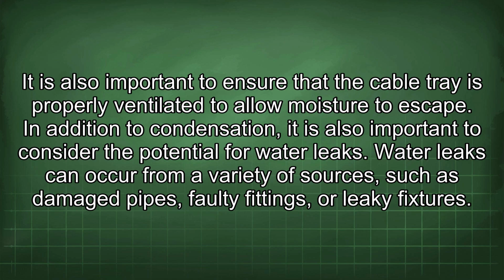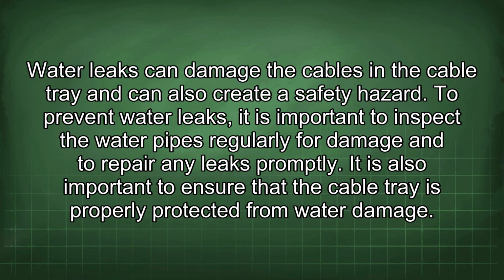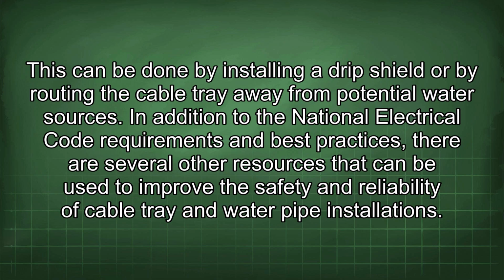In addition to condensation, it is also important to consider the potential for water leaks. Water leaks can occur from a variety of sources, such as damaged pipes, faulty fittings, or leaky fixtures. Water leaks can damage the cables in the cable tray and can also create a safety hazard. To prevent water leaks, it is important to inspect the water pipes regularly for damage and to repair any leaks promptly. It is also important to ensure that the cable tray is properly protected from water damage. This can be done by installing a drip shield or by routing the cable tray away from potential water sources.